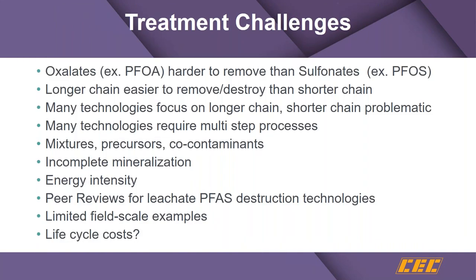Some key takeaways: carboxylates are harder to remove than sulfonates; longer chain are easier to remove or destroy than shorter chain. It's also important to consider that these technologies may be building blocks for a complete system — each one may not be appropriate by itself. They are typically energy intensive, many have limited field scale examples, and there's a lot of investigation still needed to compare life cycle costs.